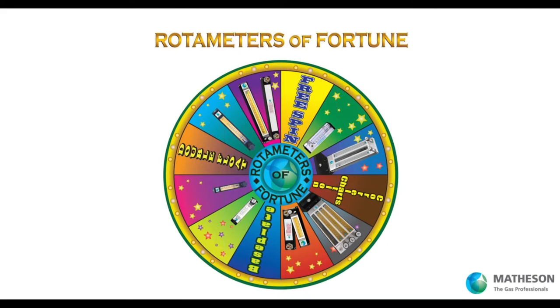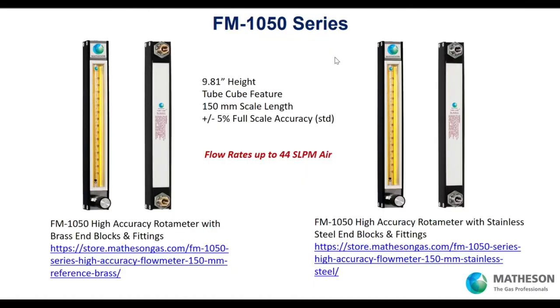Let's go to our FM 1050 — used in the reference chart example. It's a nice option with good height. It's got the tube cube feature I'll talk about. The tube cube can be changed, which is very powerful — you have one rotameter and just swap out the tube to change your application. The scale is 150 millimeters and full-scale accuracy is plus or minus 5%. This rotameter can actually achieve plus or minus 1% if we do the testing to confirm that.